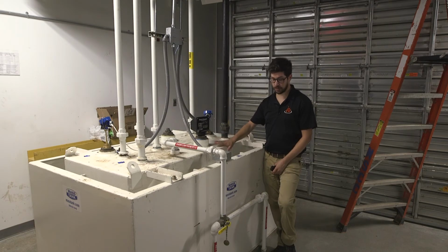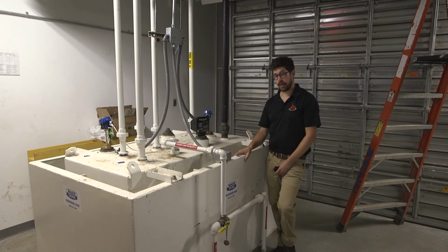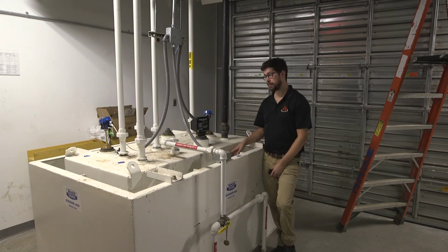Working capacity is reduced down to 225, which is 90%. This outer containment is going to be a 500-gallon containment. So of course, if this ruptures, you've got more than enough. And then we even have some extra if it continues pumping.